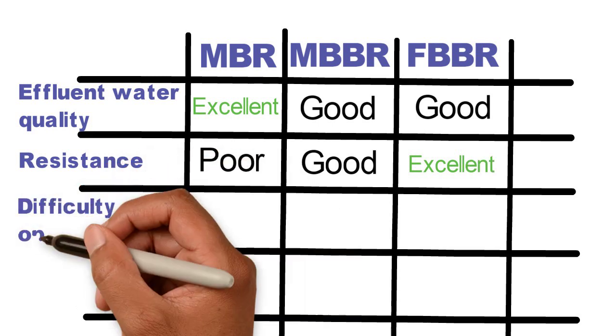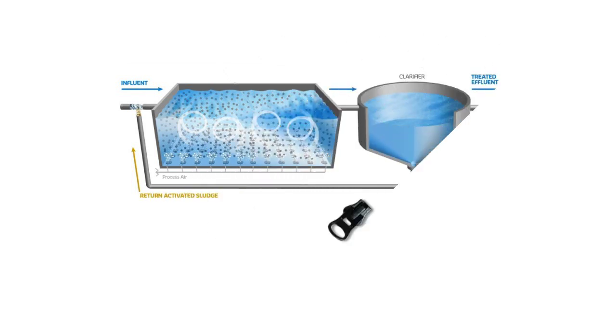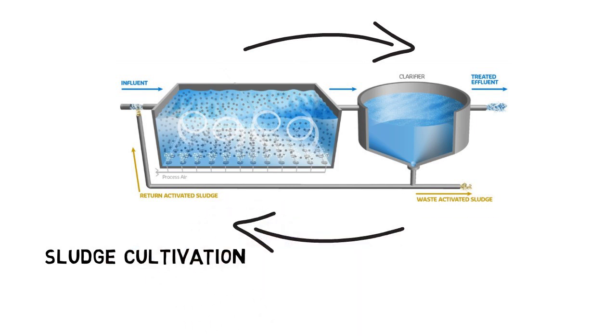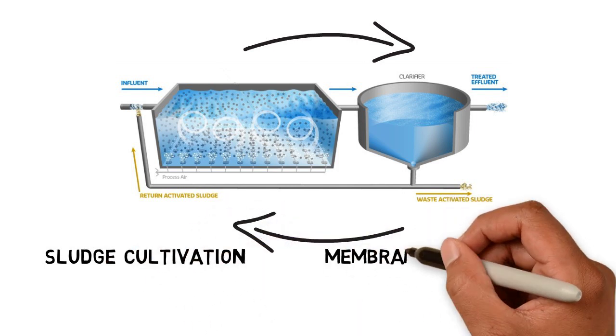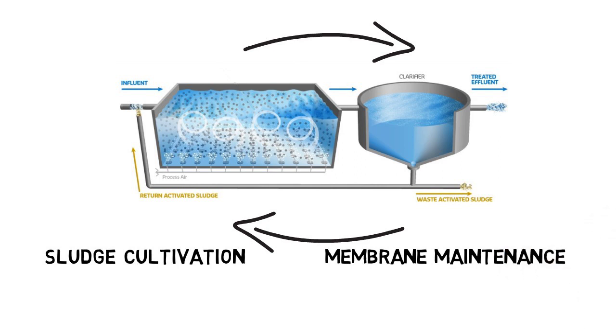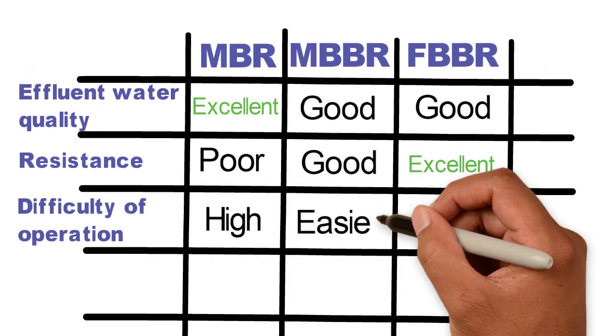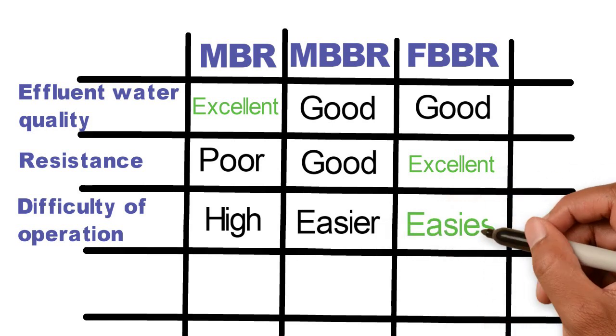Difficulty level of operation. MBRs require monitoring of the activated sludge process as well as back washing of the membranes in certain intervals. Therefore their operation can be challenging and higher qualifications are necessary. MBBRs and FBBRs are more forgiving and especially FBBRs are easy to operate.